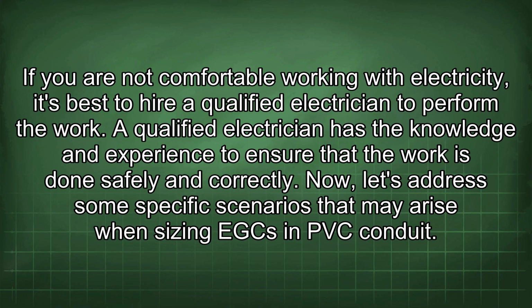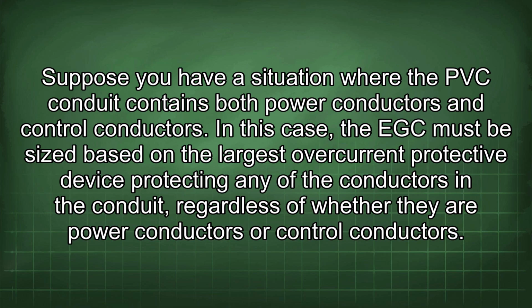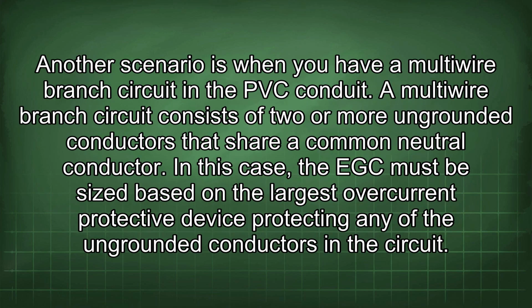Now, let's address some specific scenarios that may arise when sizing EGCs in PVC conduit. Suppose you have a situation where the PVC conduit contains both power conductors and control conductors. In this case, the EGC must be sized based on the largest overcurrent protective device protecting any of the conductors in the conduit, regardless of whether they are power conductors or control conductors. Another scenario is when you have a multi-wire branch circuit in the PVC conduit. A multi-wire branch circuit consists of two or more ungrounded conductors that share a common neutral conductor. In this case, the EGC must be sized based on the largest overcurrent protective device protecting any of the ungrounded conductors in the circuit.